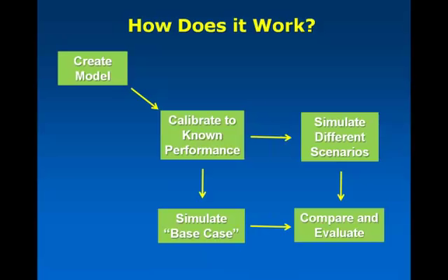You set up a model, you calibrate it so that it's representative of that real wastewater treatment plant, that specific plant, and then you run some simulation scenarios to investigate what happens if I make a change to this plant, and where am I going to be, and is that going to make us better or worse?